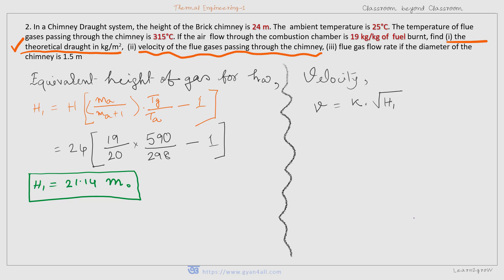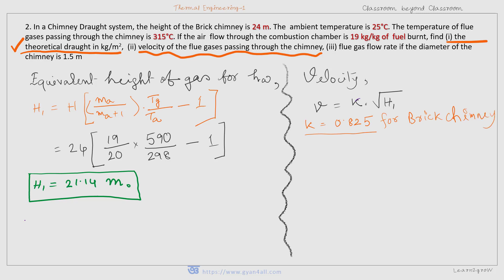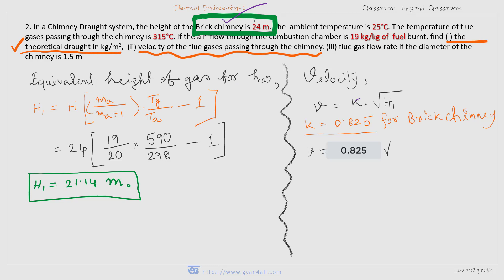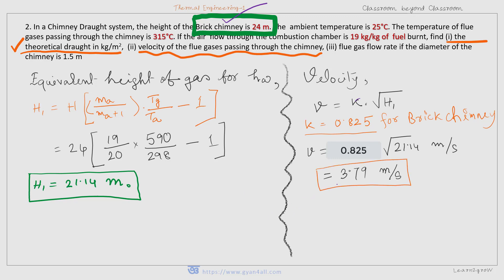Velocity of flow V is equal to K multiplied by root over H1, where K is a factor which depends upon the material of the chimney. For brick it is 0.825, and for steel it is 1.1 — it depends on the friction. Since the question states a brick chimney of 24 meters, we put K equal to 0.825. Solving it, we get 3.79 meters per second — that is the velocity of flue gases passing through the chimney.